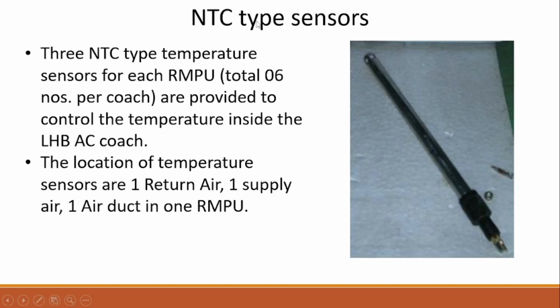NTC type sensors. There are three NTC type temperature sensors for each RMPU, which makes a total of six sensors per coach, provided to control the temperature inside the LHB AC coach. The locations of the temperature sensors are one in the return air, one in the supply air, and one in the air duct of each RMPU.